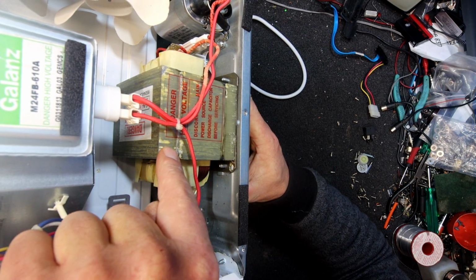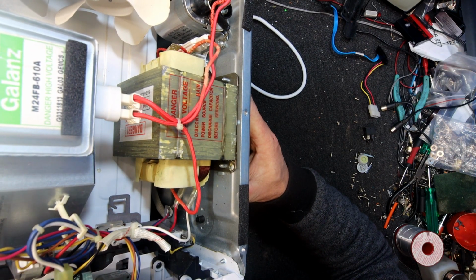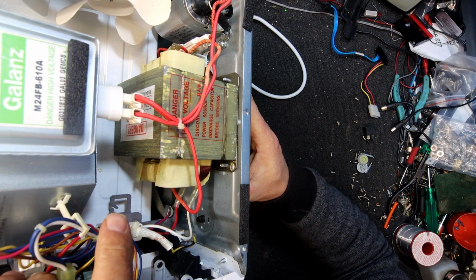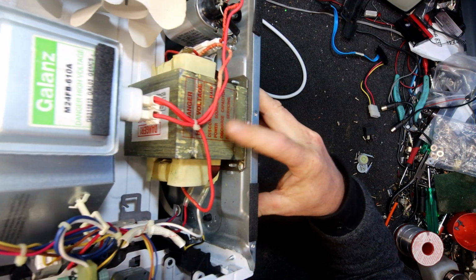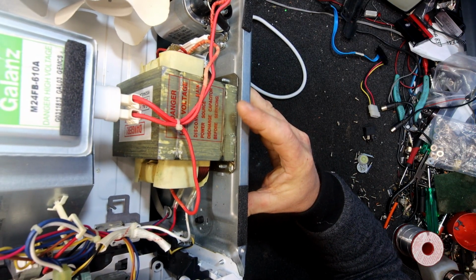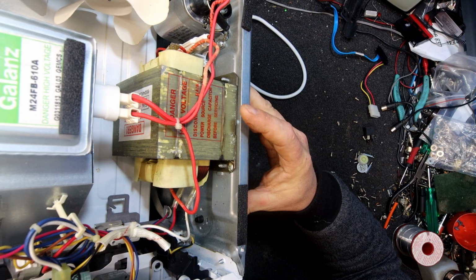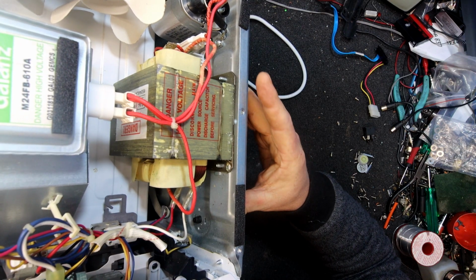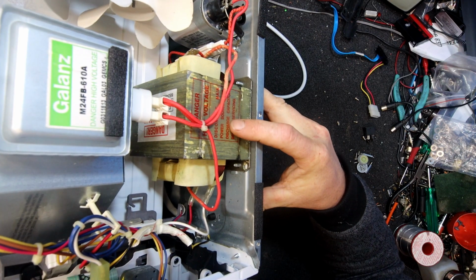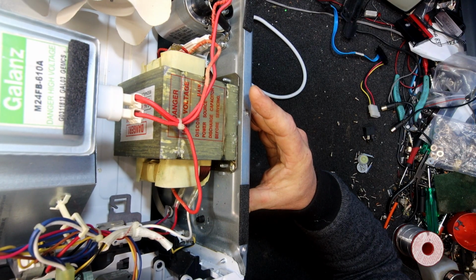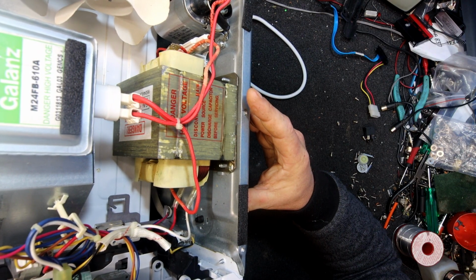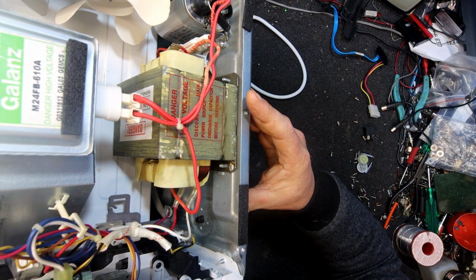But this thing steps up - so 240 volts comes in once the controller tells the relay in here to turn on. They've got safety gear in here, so if the door's open there's no way you can start this part up. There's even often a monitor switch in there which can short things out, so if power does try to get to this thing while the door's open, it'll blow the fuse. That's one of the things to look at if there's a fuse blown in these things.